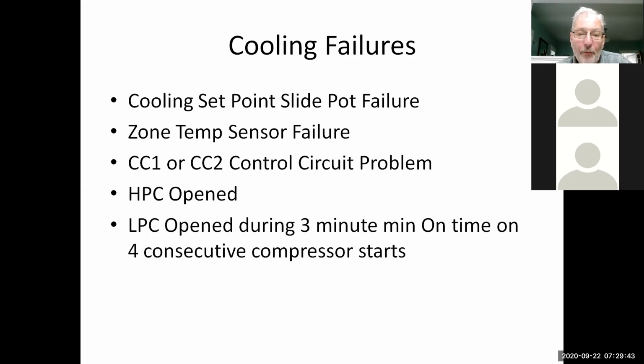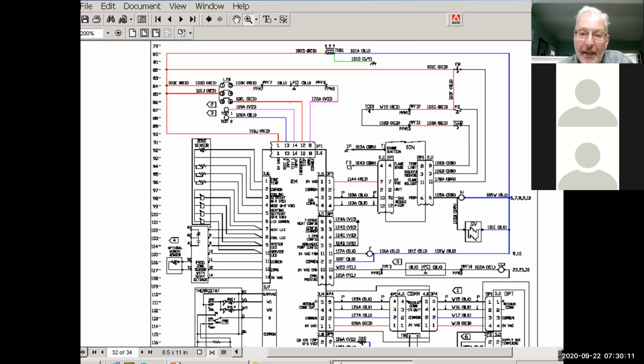But typically on a cool fail, it's going to be, again, a high pressure switch or low pressure switch opening 4 consecutive compressor starts. So if that's the case, then we're looking at low charge, maybe restricted orifices, maybe loose belts, dirty filters, the usual stuff. So if you're in a cool fail, again, the compressor is going to shut off, as well as the fan. The fan's going to shut down, lock down too. But again, if you go to those terminals and get that diagnostic, it'll kind of point you in the right direction.